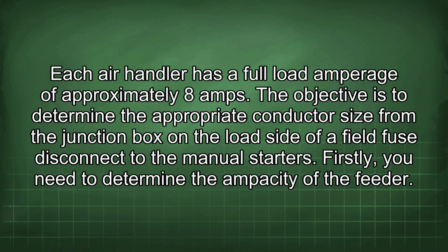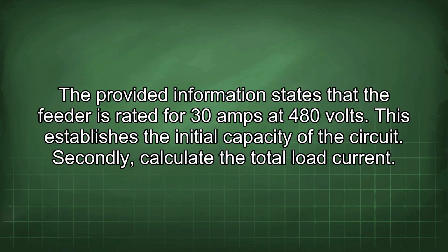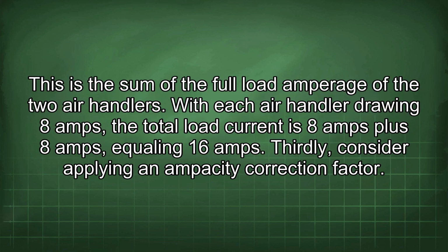Firstly, you need to determine the ampacity of the feeder. The provided information states that the feeder is rated for 30 amps at 480 volts. This establishes the initial capacity of the circuit. Secondly, calculate the total load current. This is the sum of the full load amperage of the two air handlers. With each air handler drawing 8 amps, the total load current is 8 amps plus 8 amps, equaling 16 amps.